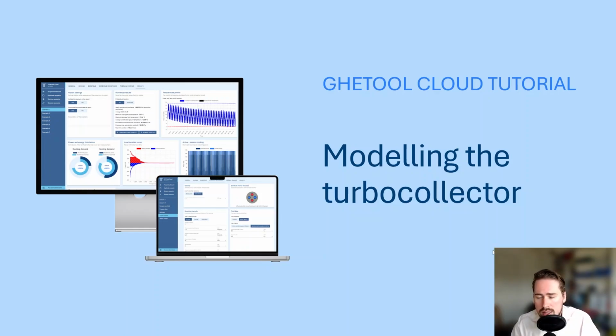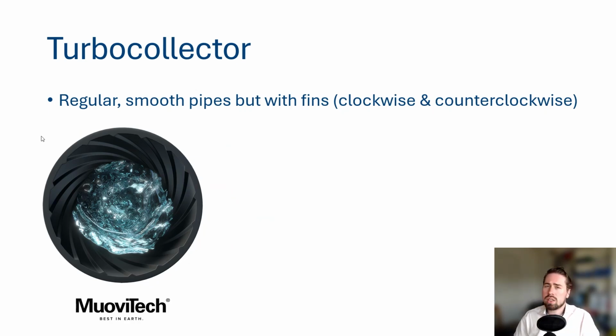So the Turbocollector is an innovative type of heat exchanger by Muovitech, and what they did is they have a regular smooth pipe, but they installed fins in it in the extrusion process. An important thing is that these fins rotate both clockwise and counterclockwise. So when you move down the pipe, you see the fins rotating in both directions. And the philosophy of this design with these fins is to induce turbulence at a lower flow rate.